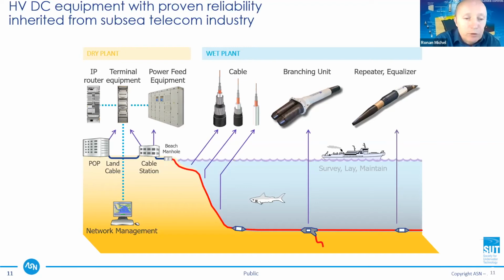but still running at 1 amp constant current. It's a bit different from the power distribution you get at home, where you have constant voltage and parallel distribution, which means that you can put your equipment anywhere and draw the current from a parallel line. Here it's in series. It has a number of benefits that we'll talk about a bit later.